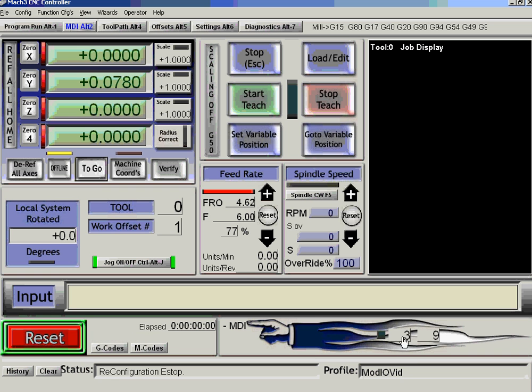Now it's config number 3 which is causing us problems. That's just because it was the first one that was scanned, I guess. And the error code is 9, which means timeout. If we put the power back on, Modbus protocol recovers. So no error, and -1 for the error line that's referred to.